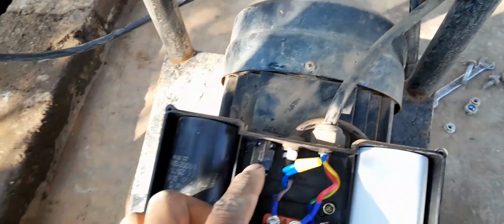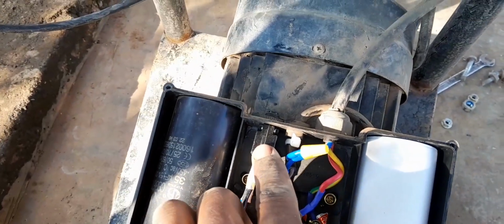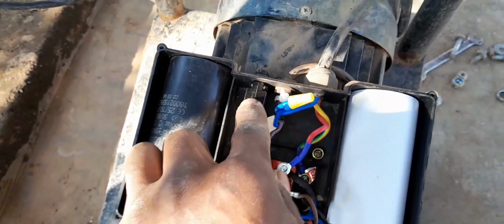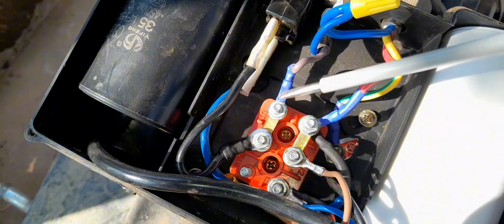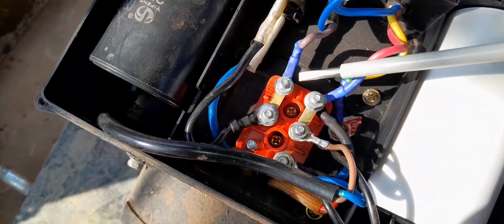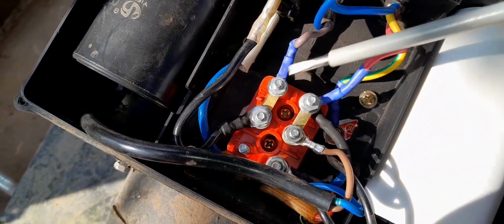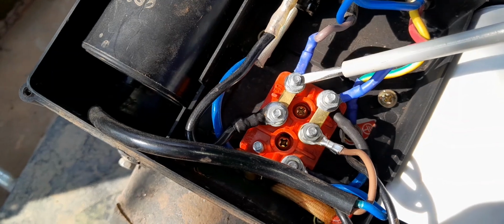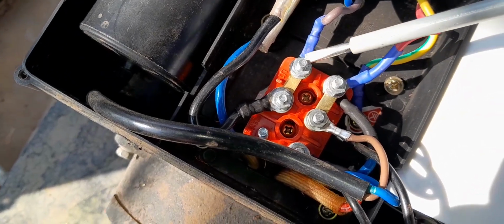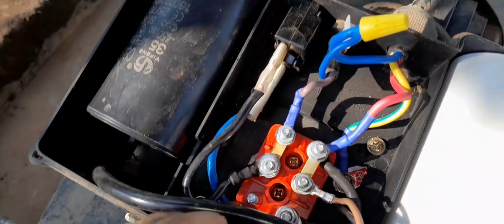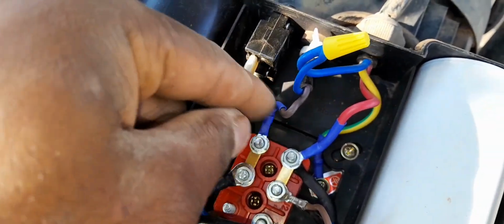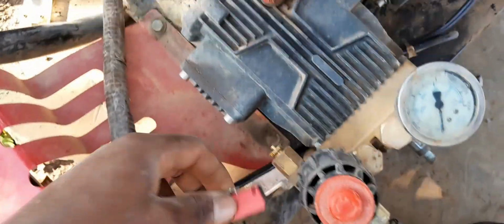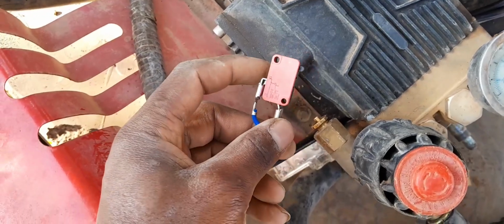So when I came, like I said before, I checked whether our switch is working correctly, which it was, but our neutral cable right here had power. And our neutral cable having power can only mean one thing: the neutral, or the power, is not going back to the source. The next appliance that was there after this neutral that had power is this one right here, and automatically this became a suspect.